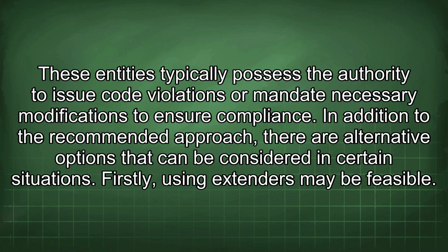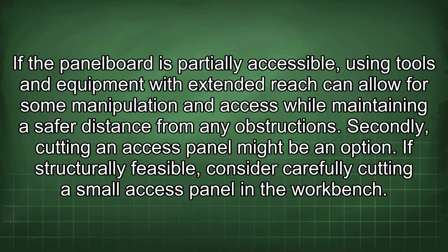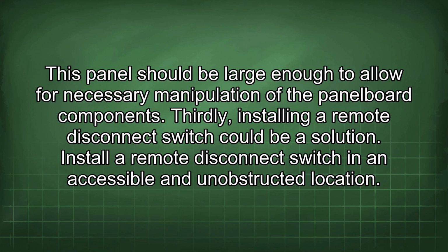Firstly, using extenders may be feasible. If the panel board is partially accessible, using tools and equipment with extended reach can allow for some manipulation and access while maintaining a safer distance from any obstructions. Secondly, cutting an access panel might be an option. If structurally feasible, consider carefully cutting a small access panel in the workbench. This panel should be large enough to allow for necessary manipulation of the panel board components.